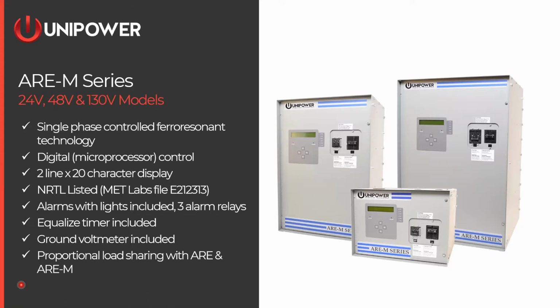The alarm lights are all included with 3 standard alarm relays, and there are additional alarm relays available, as John mentioned. Equalizer timers always included, as well as a ground voltmeter, and proportional load sharing with the ARE and ARE-M both. So as John said, most of the time that's 2 units to do load share, but you can stack more than 2 units together and equalize the load share.